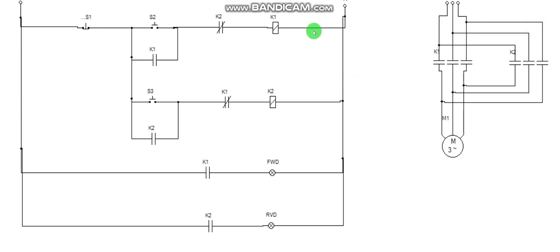So if you do that now, the second design that is controlling another motor is going to run the opposite way because you have revised this particular incomer. So you don't have to revise here, because any other power you extend this supply to will run in that same revised direction. That is always the disadvantage if you revise from the incomer. So always revise from the outgoing.